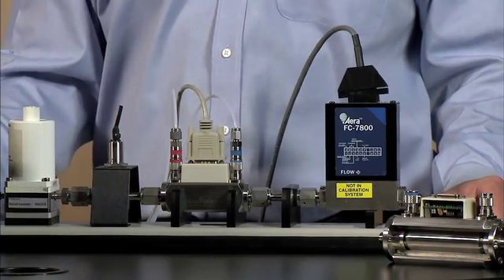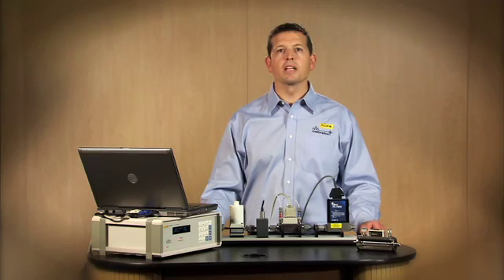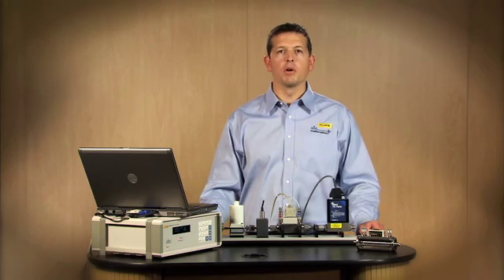The system uses laminar flow elements called Molbloc-L and sonic nozzle elements called Molbloc-S to measure flow from less than one SCCM to over 5,000 liters per minute with a single user interface.